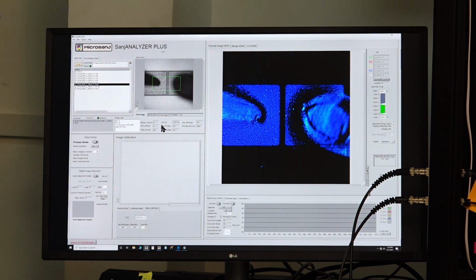The main purpose of this is that before we use the calibration map, we have to correct it for any thermal expansion. To correct it for thermal expansion, we click an option called correct XY. So we click on this option, and the moment we click it, the XY correction is done. So we have to now save this image. To save the corrected calibration map, we go to this option called save images / data.